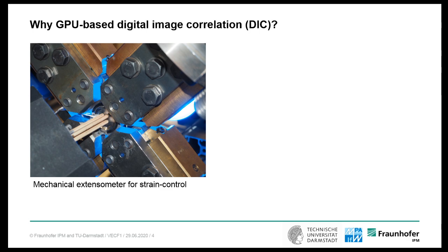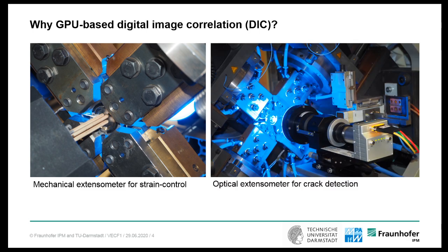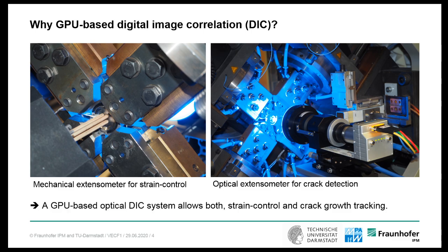Why is it worth to develop a new GPU-based digital image correlation system? Because many crack growth experiments use two sensors for strain measurement. The first one is a mechanical extensometer for strain control because this has measurement rates in the kHz range. The second one is an optical DIC system because that provides the spatial resolution for crack growth measurements. A GPU-based DIC system is able to do both strain control and crack growth tracking.